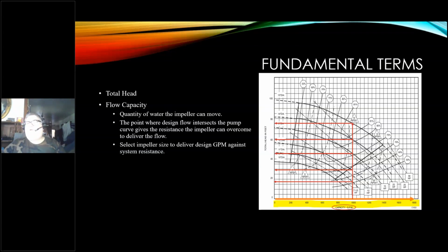So if you had resistance above 75 feet, your flow is going to go down. It moves the line to the left if your resistance is higher than 75 feet. Conversely, if it's below 75 feet, it moves the line to the right, and you can actually pump more. So the higher the resistance to flow, the lower your flow. The less resistance to flow, the higher the flow. So the less the head, the higher the flow.